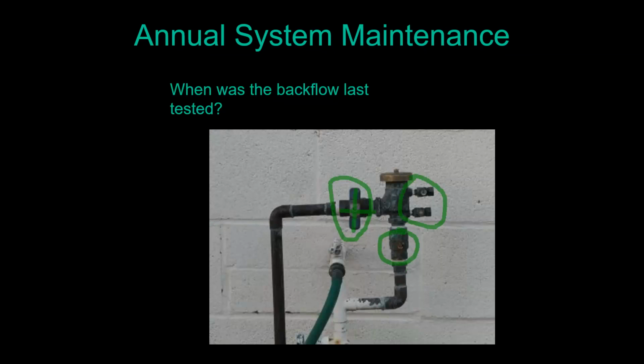So let me clear these real quick so I can draw some new lines. Okay, get my pen back. There we go. So what these do is they make sure the water, once it goes in your irrigation system, can't come back into your drinking water if the water tries moving in a backwards direction. There's a valve here that opens this way, so that creates an air gap underneath this cap. And there's also another check valve down here that shuts to seal off that pipe, so that water from the irrigation system cannot go back into your drinking water system. So that's a good thing.